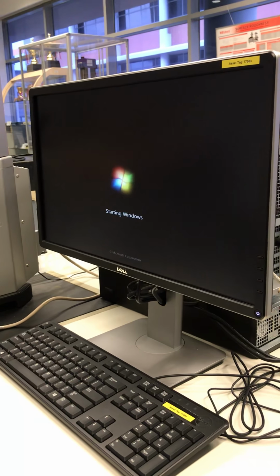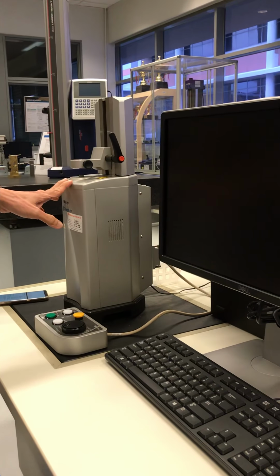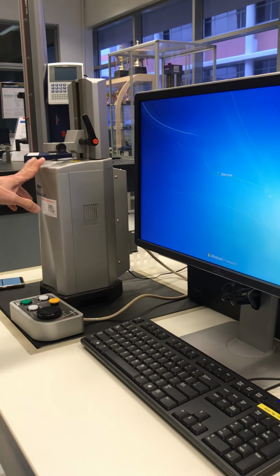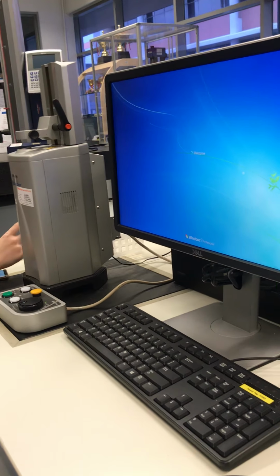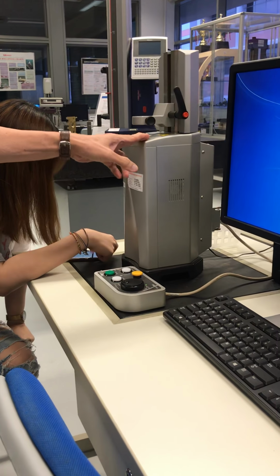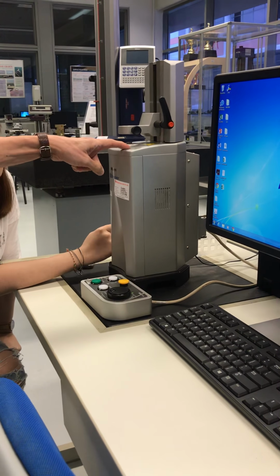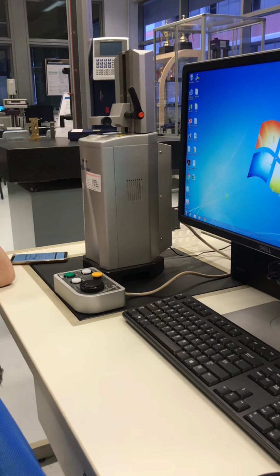Remember this is a dial checker or dial calibrator, we call it eye checker. And every year, although we are in training, we need to send this one for calibration. You send it to an accredited laboratory.